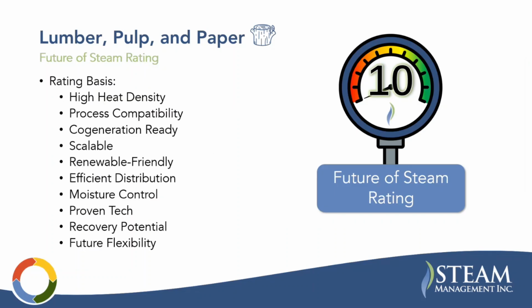Future of steam rating here: a 10. Like I was just saying, because of low fuel costs, steam is a good option. It delivers large amounts of heat efficiently. They have high heating requirements, and it's already integrated into core operations like kraft mills. It's cogeneration ready, so they can utilize it to satisfy large power requirements at the mills and generate their own power. It's scalable, and it's renewable-friendly, so it can be powered by byproducts like biomass or waste liquids like black liquor in recovery boilers.